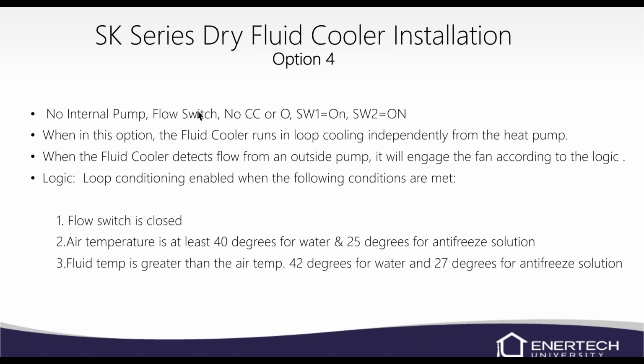So when the flow switch is closed, the air temperature is at least 40 degrees for water and 25 degrees for the antifreeze solution. And when the fluid temperature is greater than the air temperature. So that'll be your 42 with the deadband of 2 degrees, so you have 42 and 27. So it's going to make sure that these conditions are met, and then it'll run.